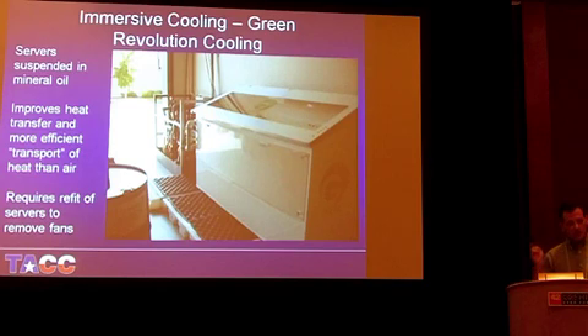There's one other thing we have to do on the servers: the thermal paste normally used for processors actually degrades and dissolves in mineral oil, so it gets replaced with a thermal paste that doesn't dissolve in the oil.